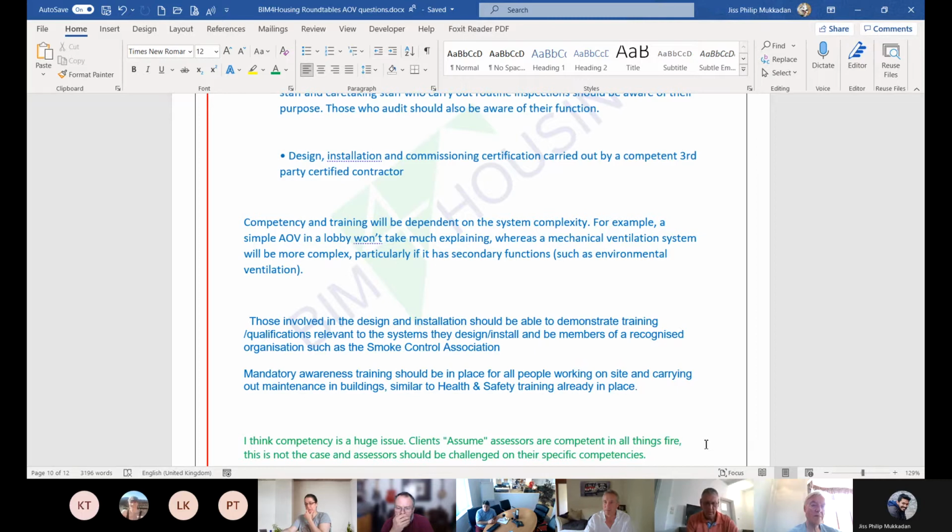It's something I see all the time. We've just had it with a hospital that's using our software to do their fire doors. For the last 3 years, they've been inspecting 2,500 fire doors. They actually only had 700 doors that were acting as fire doors.